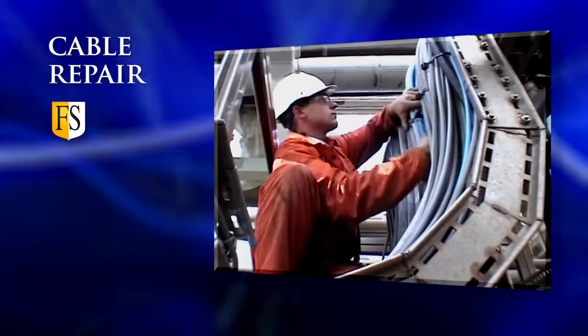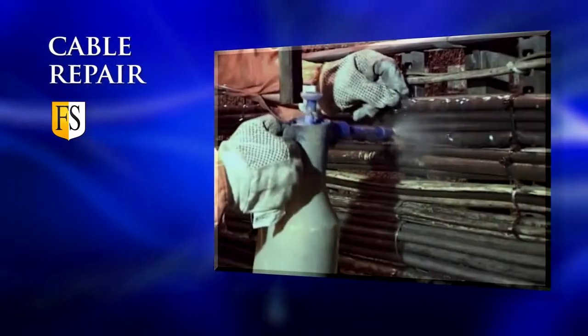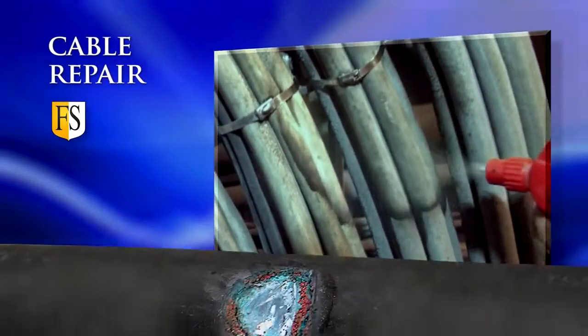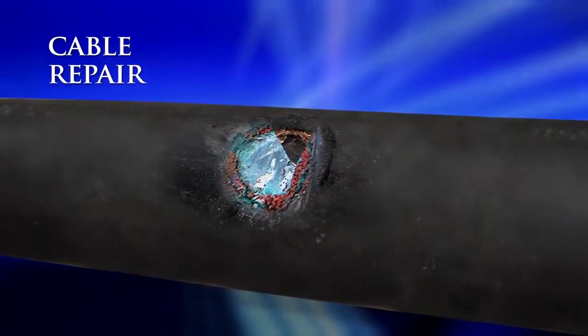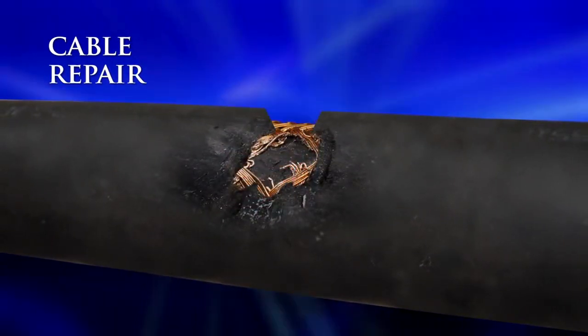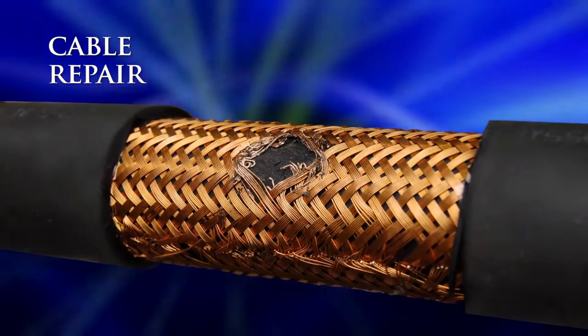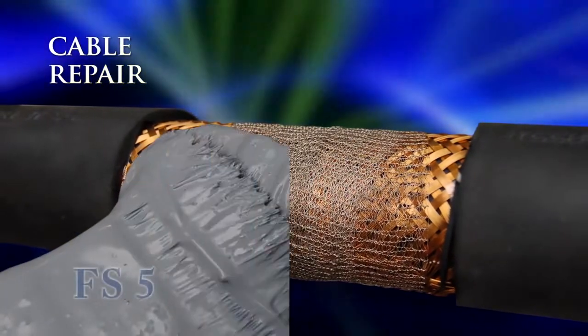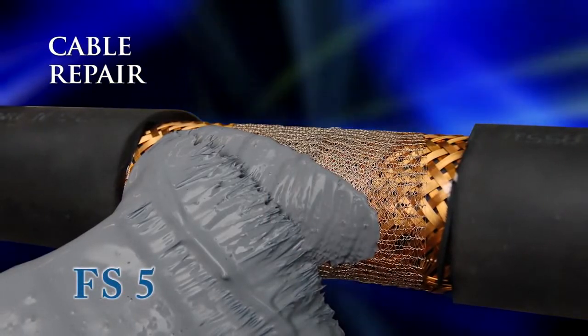When our team performs a repair and fire protection, we clean the cables using special cleaning materials or water. If the outer sheath and the cable's screen is damaged, we clean the affected area and rebuild the screen by use of a metal shielding tape. We then apply FS5 coating.